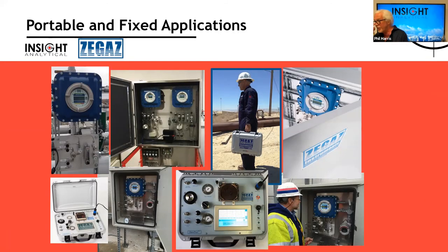The analyzer is available as both a portable unit, which we show down here, kind of suitcase size. So if you want to do testing at a facility, if you're a service provider who does testing work for plants to see if, you know, are you guys on spec? The portable is available. Fixed installations, especially in Canada, we'll often put them in a cabinet of some kind because we want to protect them against the cold out there. But when we're in temperate regions, you'll see these analyzers just mounted directly outside, right at the pipeline.